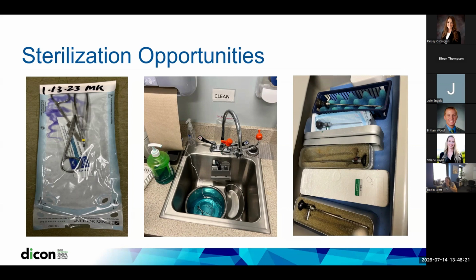In the middle picture, our sink is backed with incorrectly prepared enzymatic detergent. In fact, this detergent, I believe, was prepared at the beginning of the day, and stainless steel instruments were placed directly in that solution throughout the day. Prior to the end of the workday, staff would then utilize their reusable, not disposable, brush to manually decontaminate those items. And we still have pre-prepared enzymatic detergent in a non-manufacturer approved dispenser.